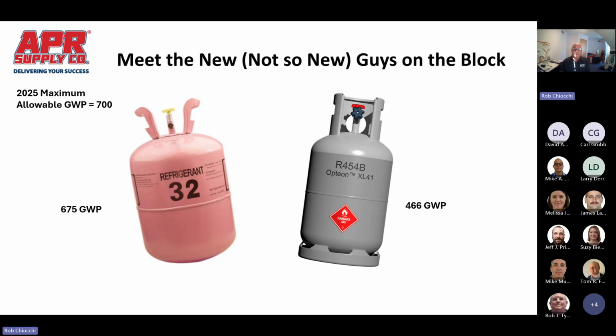So as you can see, R32 at 675 global warming potential is pretty close to that ceiling of 700. Unfortunately, R32 is living under the constant threat that due to environmental impacts, that 700 threshold might be lowered to 600 over the next 5 years. This would create a great rift with R32, as it would no longer be able to be used in equipment if they lower that threshold to 600.